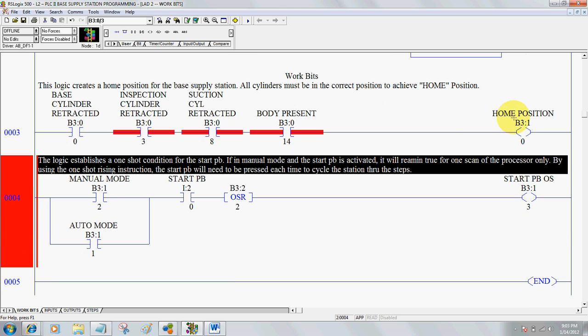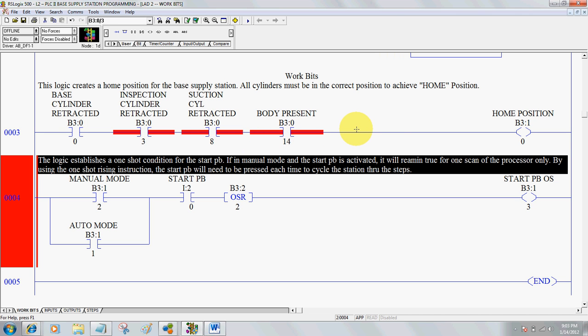Next we want to create a home position. Home position is nothing more than all cylinders being in their normal or safe operating position, which is usually retracted. Here you can see I've programmed B3:00 for base cylinder retracted, and additional input conditions: B3:03 for inspection cylinder retracted, suction cylinder retracted, and body present — meaning a part is available. This is not all of the instructions required for home position, but it's a good start.